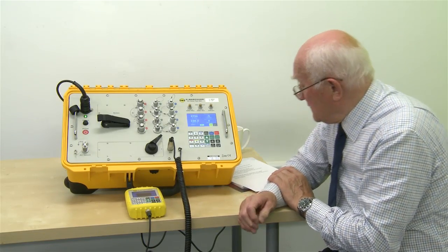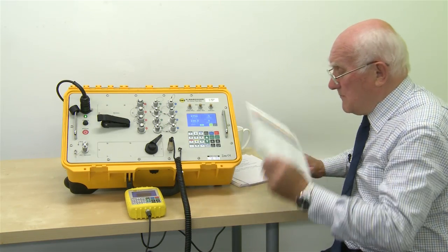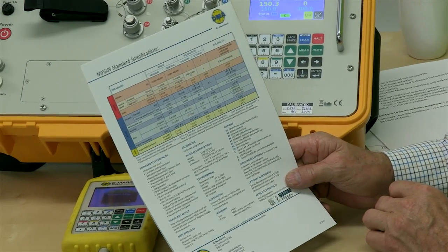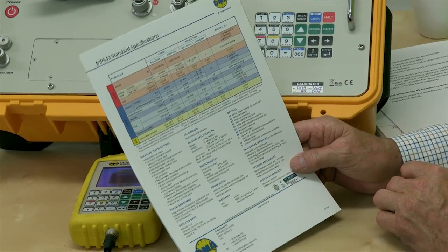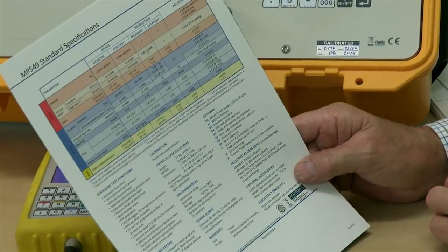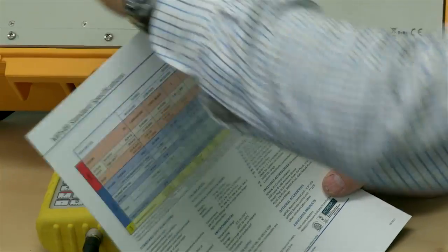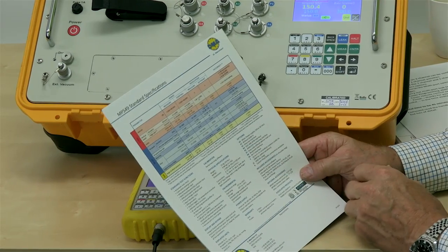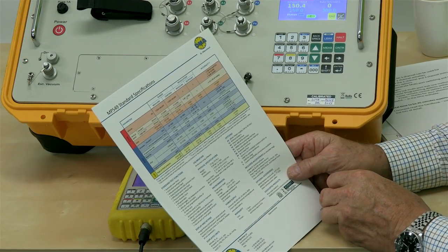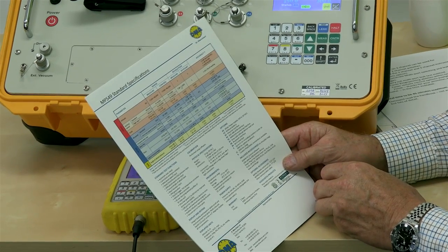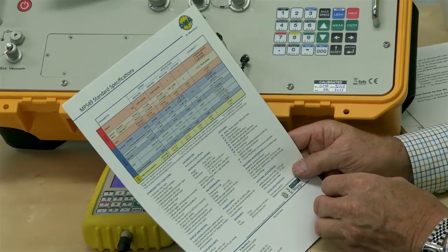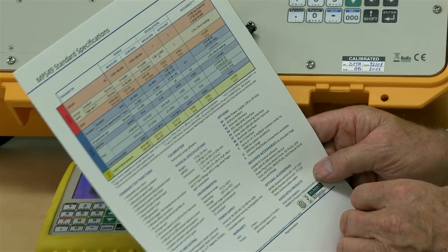Equally, when we look at the data sheet, we had mentioned that it's got a whole host of options, and in there, for example, it tells you all about the remote control capabilities that you can have. This particular plate here can be removed, and you can fit into there, for example, an Ethernet interface, an IEEE 488 GPIB interface. You can have an ARINC 429 interface. We can have a grey code device readout. We can have Bluetooth if you wish, and a Wi-Fi interface.